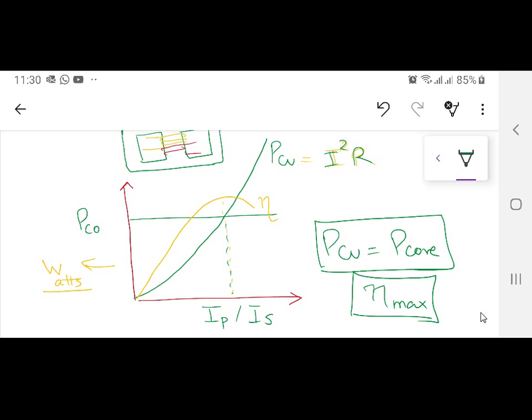But whenever this transformer is designed for household community, their peak time is approximately at 4 or 5 pm to 9 or 10 pm. And they are designed in such a way that their maximum efficiency point is going to be at a load of approximately 70 to 80%.